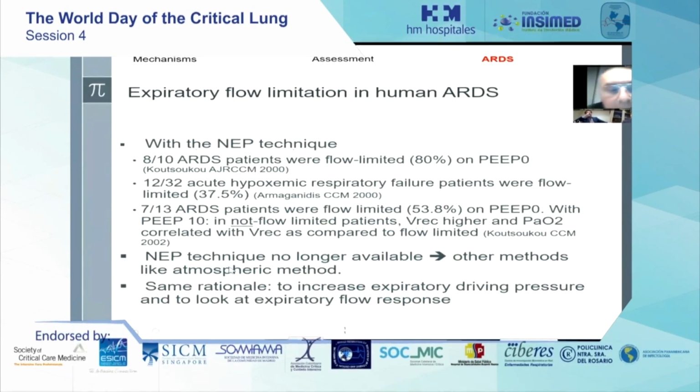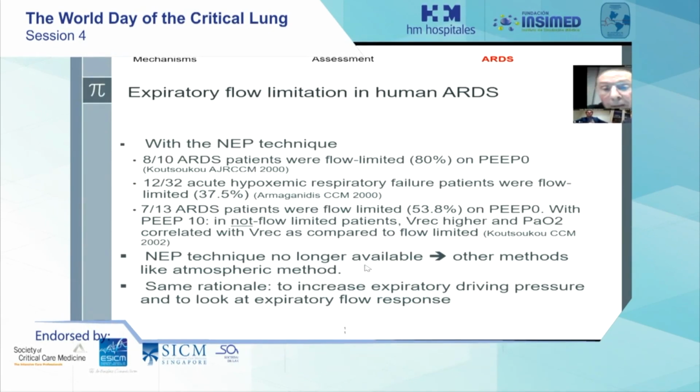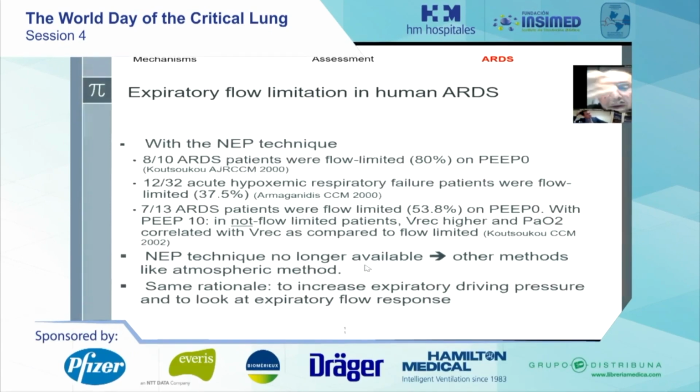But now the NEP technique is no longer available because it is not allowed to have a negative pressure in the ventilator circuit. Therefore, other methods can be used, like the atmospheric method, which is based on the same rationale: you are going to increase the expiratory driving pressure and look at what happens to the expiratory flow response.